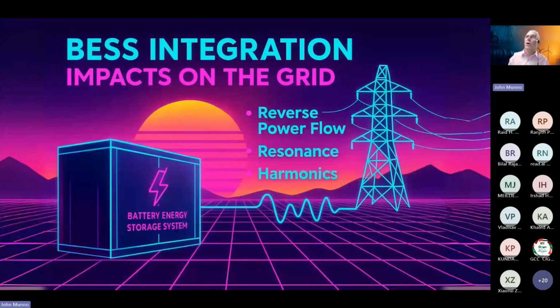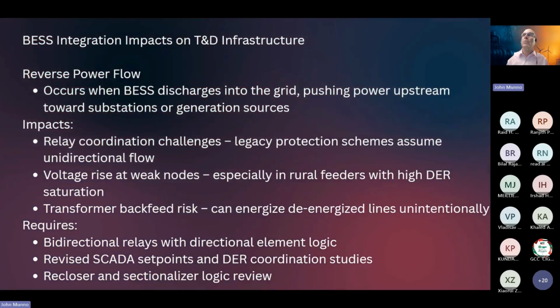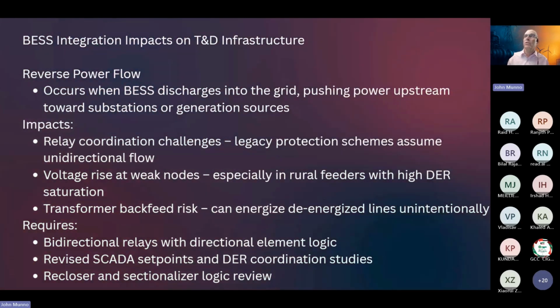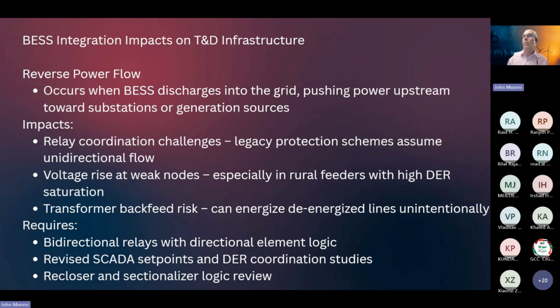Now we're going to get into the BESS integration impacts on the grid. What is it that BESS systems do to utilities and T&D systems? Let's talk about reverse power, resonance, and harmonics. Reverse power can happen when the battery system discharges into the grid, pushing the power upstream towards substations or generating sources. Most of the legacy equipment was designed for electricity flowing in just one direction. So we can impact relay coordination, and we can have voltage rises at weak nodes.